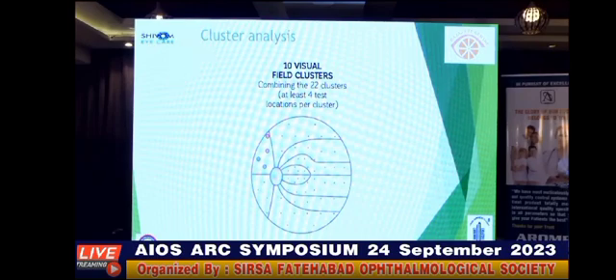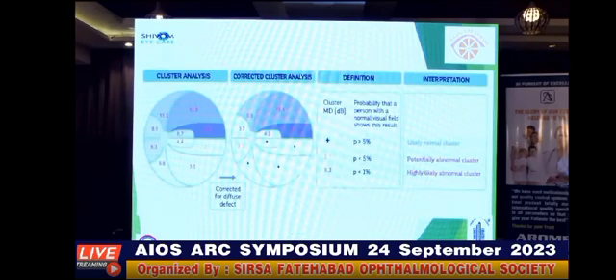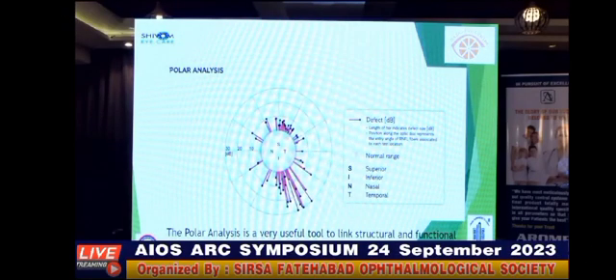Now, the cluster analysis and the polar analysis or the trend analysis, this is something that is available only on an Octopus.